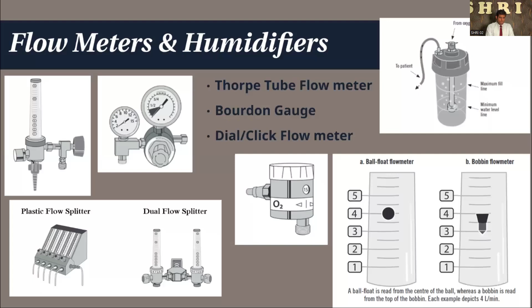All patients on ventilators require additional oxygen more than we planned, because the patient's condition can vary. We may have to go for higher settings, higher pressure levels, high FiO2, so always keep an extra amount of oxygen. As an example I mentioned here, a patient on 100% oxygen consumes 9 liters per minute. Always calculate the total volume of oxygen we need, how many new cylinders we have, and how many cylinders are half filled. Take as many full cylinders as possible, but you can't discard the half-filled cylinders. You can take them if the amount is at the correct level.